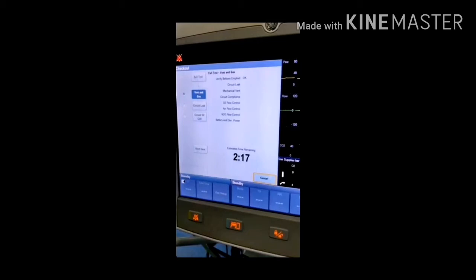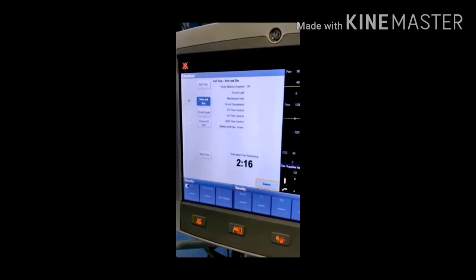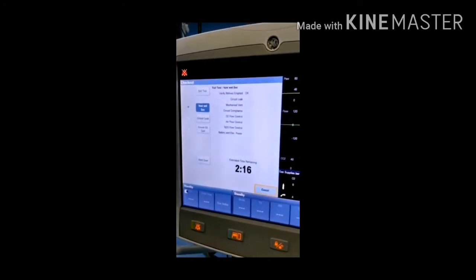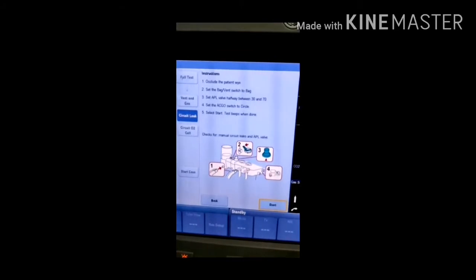When you are doing the test, just make sure that all the circuit and the connectors are connected very tightly. There is no chance of any leakage from it. Okay, that test has been completed. There is no leak. So moving ahead, there is the circuit leak test. We will occlude the patient Y. That means we have already blocked it from the previous test.